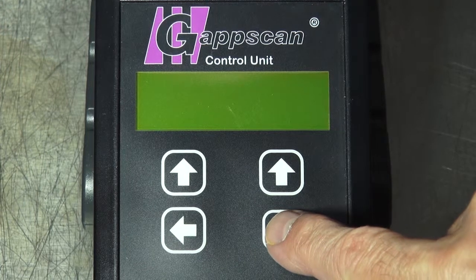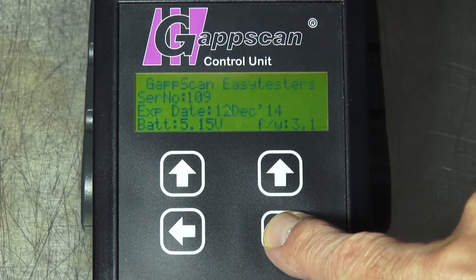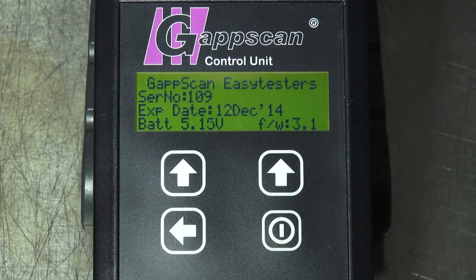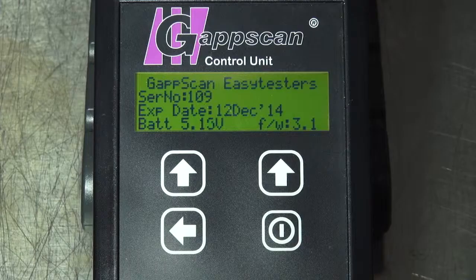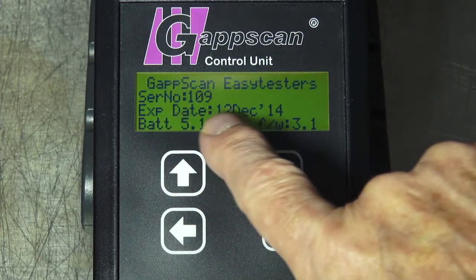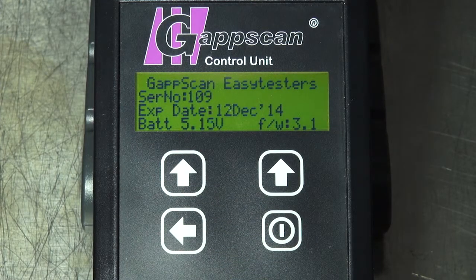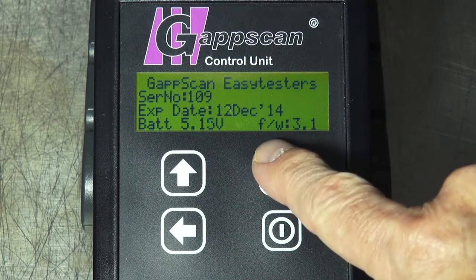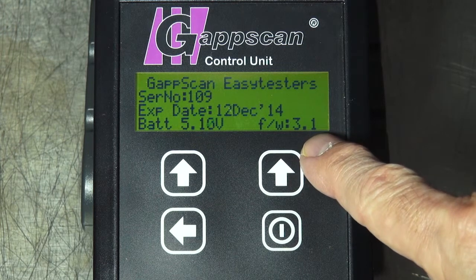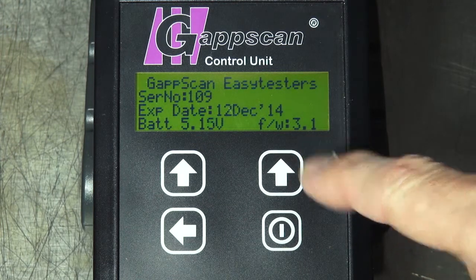Press the I/O key for 2 seconds to switch on the control unit. You will see the expiry date. Always ensure that this is within date for testing, as when expired it will not work and should be returned for calibration. You will see the battery life and the serial number. This is the firmware level, which is the version of software that has been installed.